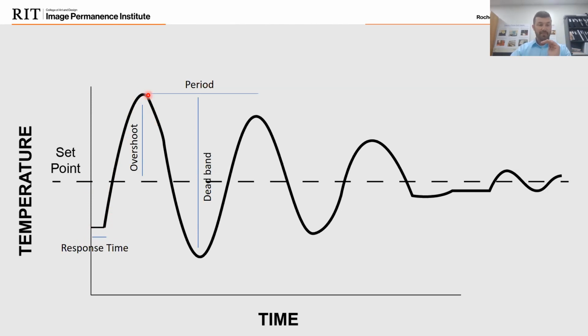Once that air handling unit stops, we'll have some drift, and we'll be in this drift, which they call the deadband. The temperature will slowly drop. We'll go from 72, 71 to 70. We cross that set point, but it doesn't come on yet. Then we maybe hit 69, maybe 68. At that point, the unit will say, okay, it's time to turn back on, and it'll try to reach the set point again. So when they discuss deadband and overshoot, this is one of the things to keep in mind. And the period is the time between when we hit temperature, then sit idle in the deadband, until the unit turns on to reach the set point again.